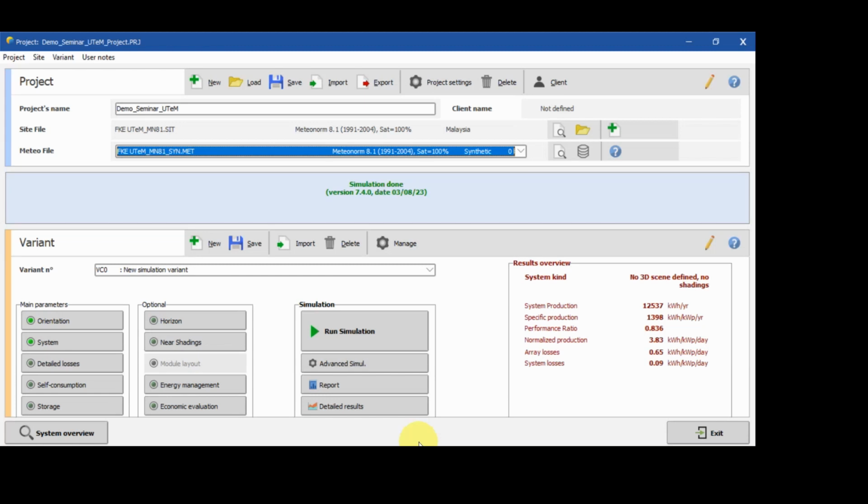Okay, so according to Mr. Hazim, this is very high, which is generally true. We want to generate 1 megawatt, but we install 1.5 megawatt. So maybe from the perspective of an investor, it seems like a waste. Right? For similar projects, I've seen different companies use ratios in the range of 1.2 up to 1.6.